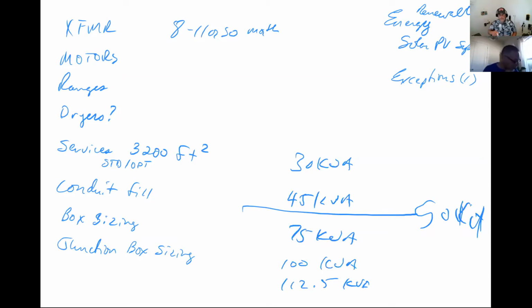Oh yeah, I think there was a question about airspace for a transformer. Airspace around a transformer would be, going back over to 450.21(A) on page 335. If I've got a smaller transformer, I can butt it straight up to the wall. Let me preface something: manufacturers typically require an air gap of at least an inch or so. But code wise, there's nothing that would prohibit me from putting it up against the wall, except where it's a dry type transformer indoors. I do have to have a separation of 12 inches from combustible material, unless separated by a fire-resistant, heat-insulated barrier. Typically, the transformer shrouding is going to be a fire-resistant, heat-insulated barrier.